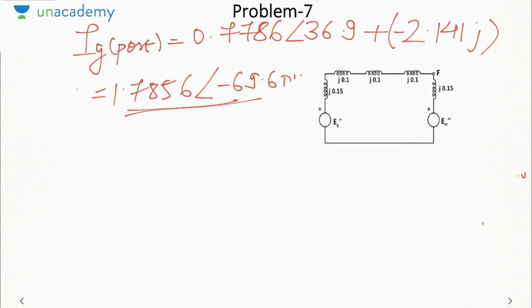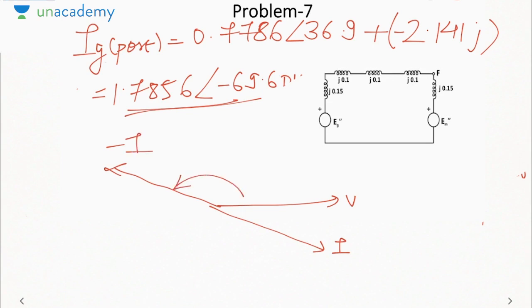How? Suppose this is the voltage, this is your current, it is lagging the voltage. Now if you draw minus I, it is actually leading the voltage. So whenever you commit an error in the direction of assumed current, you will observe that the fault current will lead the fault voltage. Why is it leading? Because the assumed direction is opposite to the actual direction, which introduces a 180 degree phase shift. Hence the power factor goes from leading to lagging and vice versa.